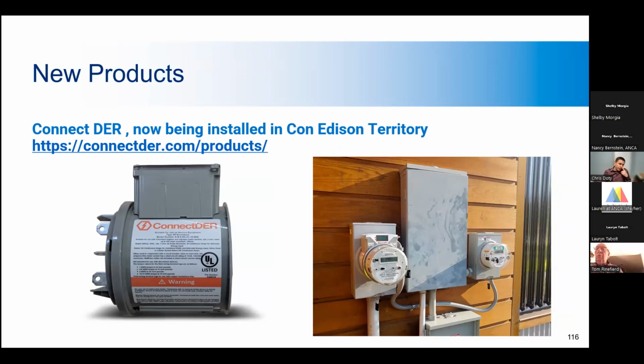And so here we have a couple new products. This is what's called a Connect DER, which can eliminate costly interconnections and reduce installation errors for supply side connections. This was experimented with in the Con Ed territory. It's installed by the utility, and it's the point of interconnection, and it gives real-time solar generation data for forecasting. This requires that the GEC connection be made in the meter pan, and the 2020 NEC requires that all meter pans have a non-fused disconnect switch so that the meter can be serviced. So that may change where the point of interconnection is. And this also allows contractors to install PV to stay outside the home while installing the system, and they don't even have to go in your home.